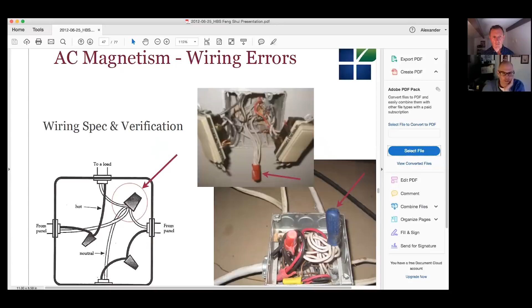Where two branch circuits are feeding one electrical junction box, like behind these two switches, or up in an attic, you find this, and they've mixed the neutrals together. If they're from different branch circuits, this is a code violation, and you find this all the time. Electricians will swear up and down, oh, we would never do that.